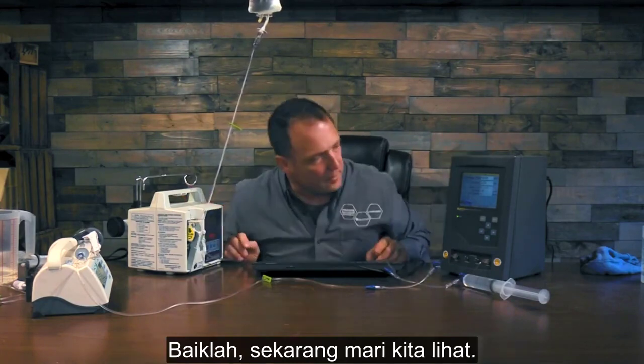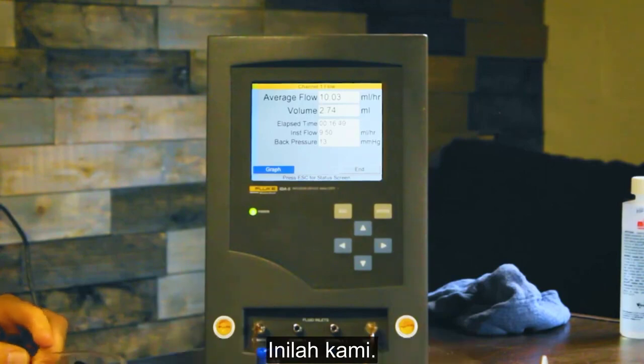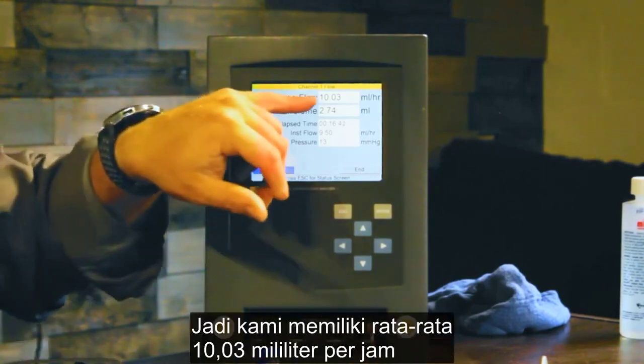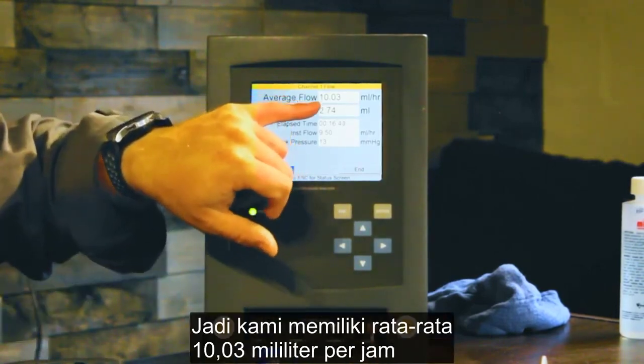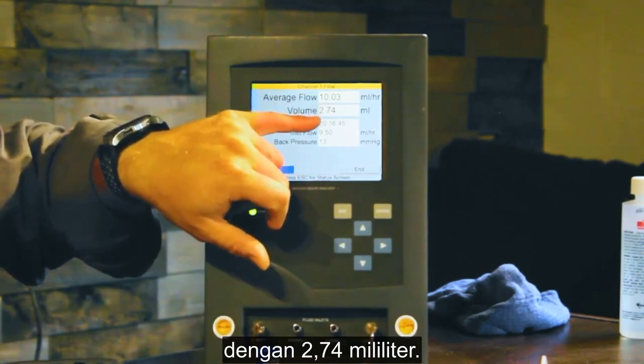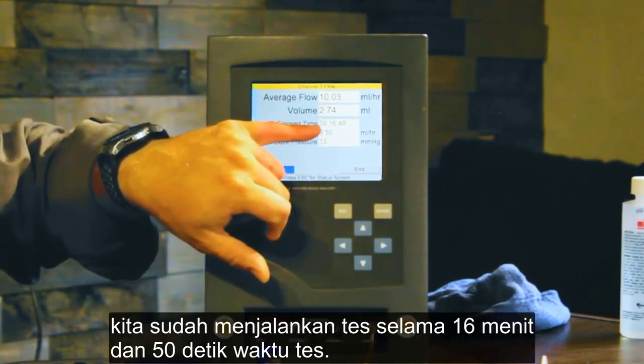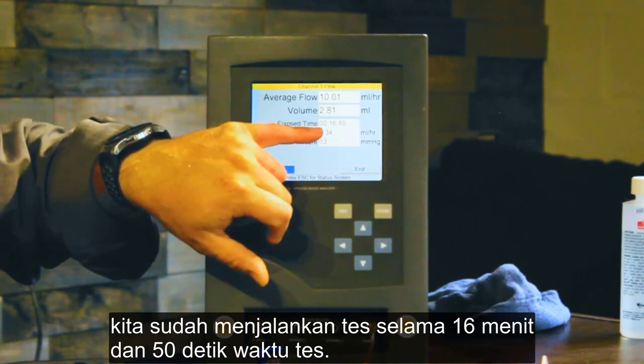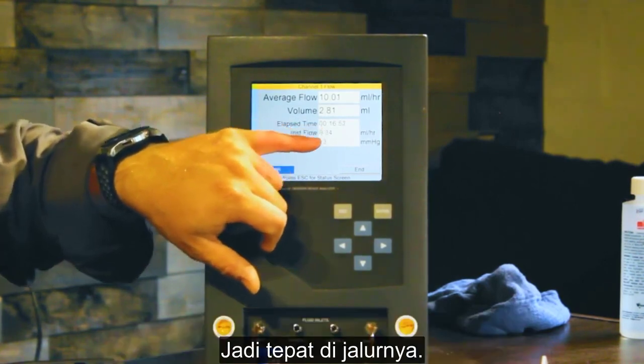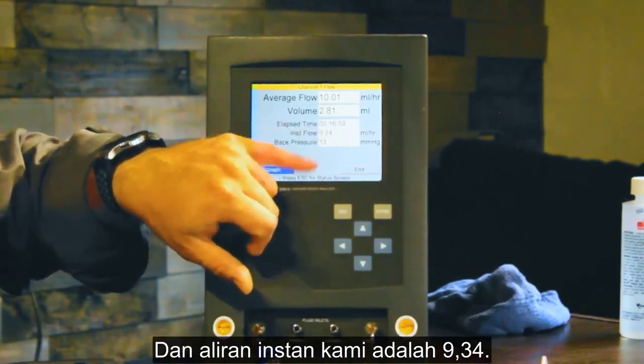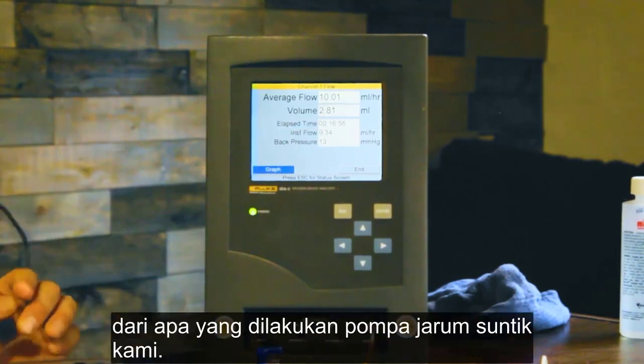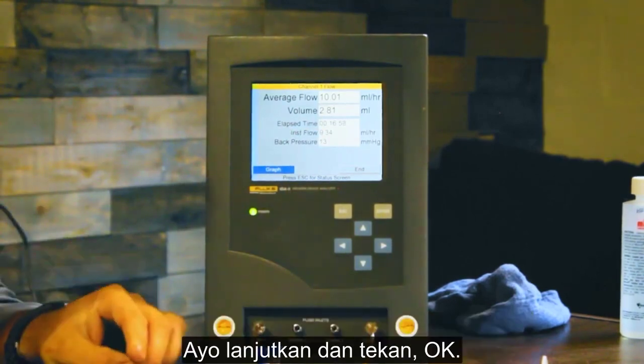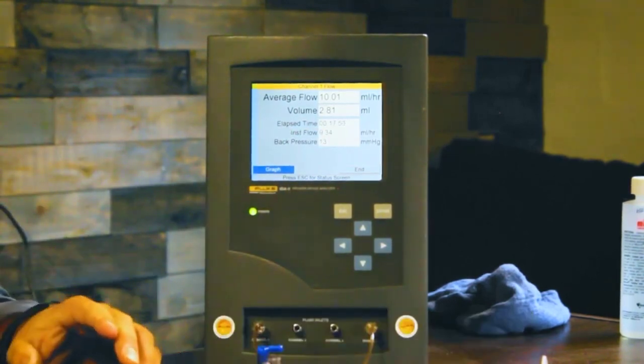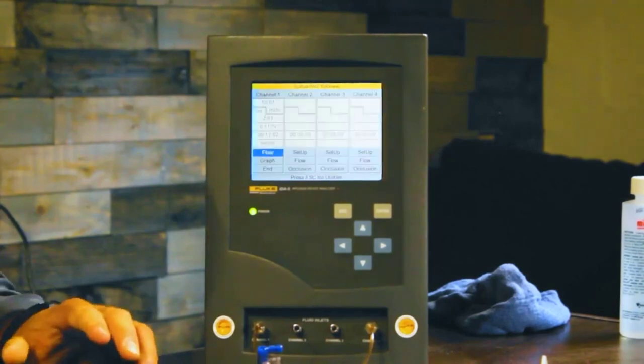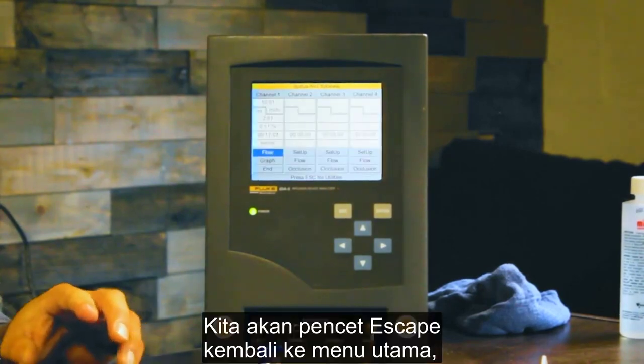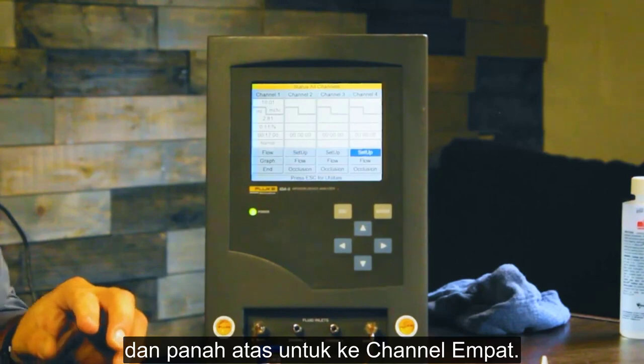Alright, now let's see, here we are, we're still on channel 1. So we have an average of 10.03 milliliters an hour with 2.74 milliliters. We've gone for 16 minutes and 50 seconds of test time, so right on track. And our instant flow is 9.34. Okay, so that's just a quick check of what our syringe pump's doing. Let's go ahead and hit OK. We're going to hit escape back to the main menu, and then arrow over to channel 4.